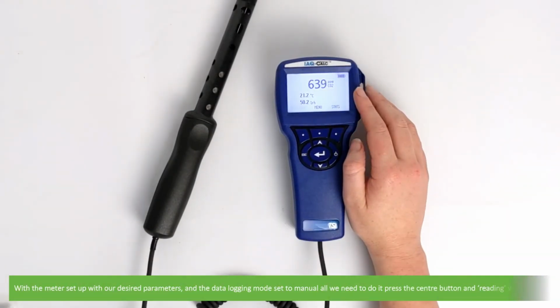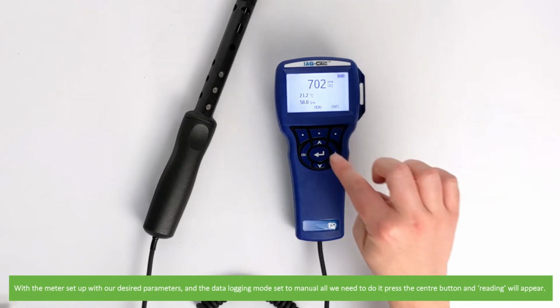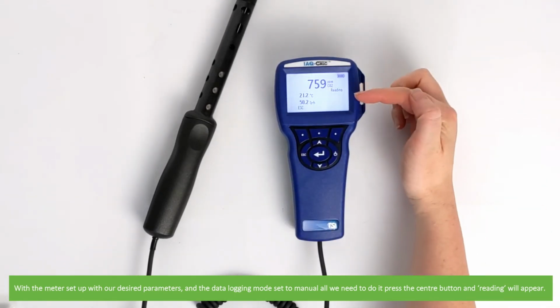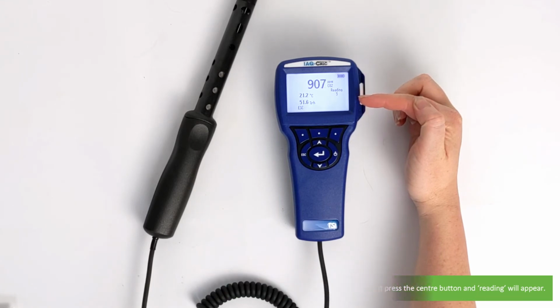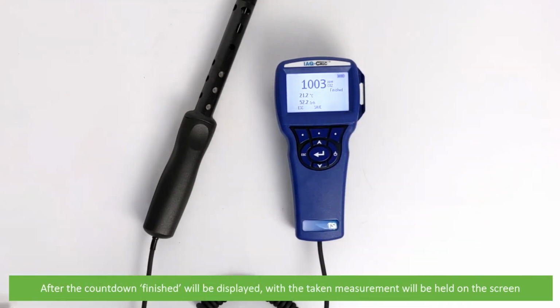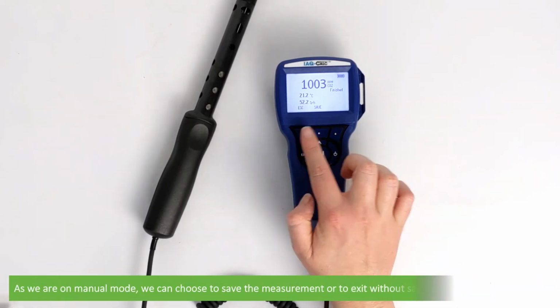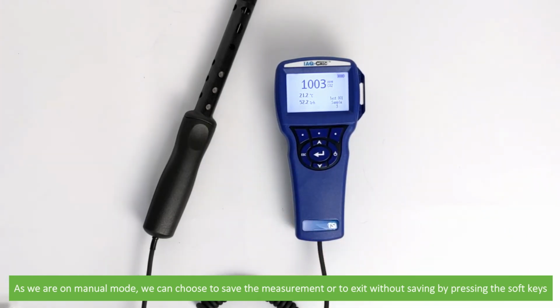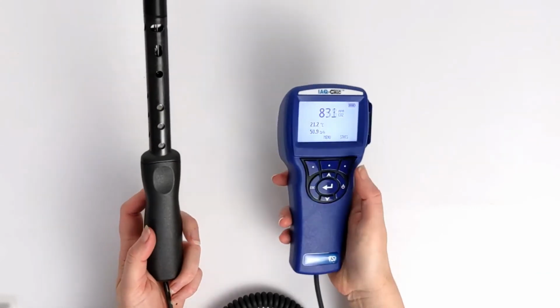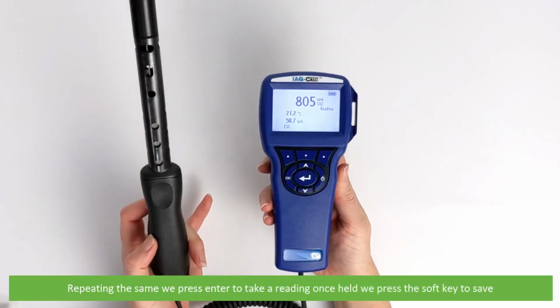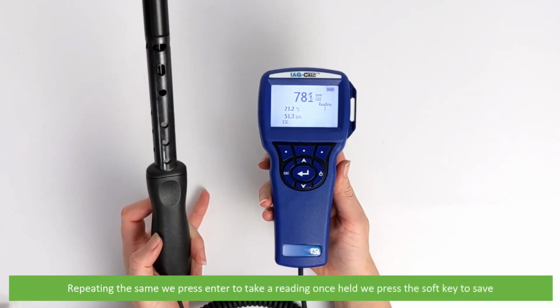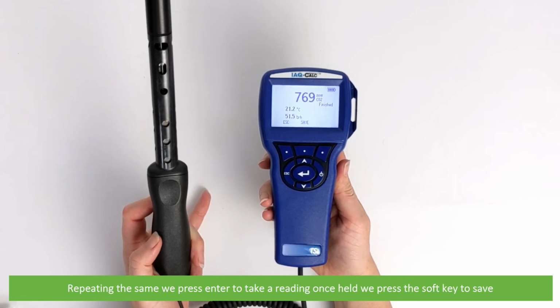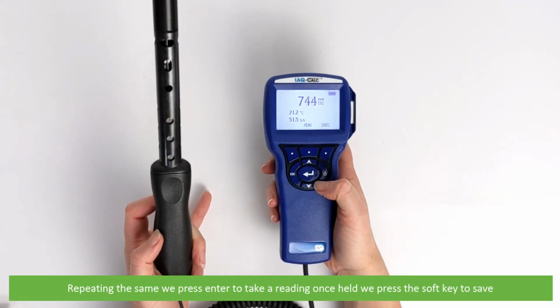With the meter set up to our desired parameters and the data logging mode set to manual, all we need to do is press the center button and reading will appear on the screen. After a short countdown, finish will be displayed, with the taken measurement held on the screen. As we are on manual mode, we can choose to save the measurement or exit without saving by pressing the soft keys. Repeating the same, we press enter to take a reading. Once held on the screen, we press the soft key to save.